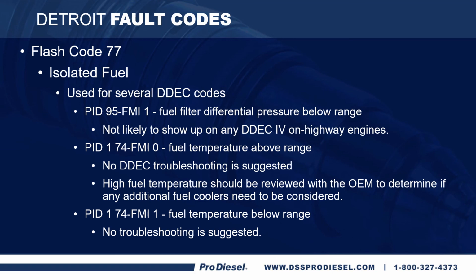This is used for several DDEC codes. A PID 95 FMI 1, fuel filter differential pressure below range, and you can see why that's not normally on any of the on-highway engines. A PID 174 FMI 0, fuel temperature above range. This might be something you need to talk to your OEM dealer about, how you can get additional fuel coolers. They need to be considered for your certain application. And a PID 174 FMI 1, a fuel temperature below range. Normally there's no troubleshooting suggested.